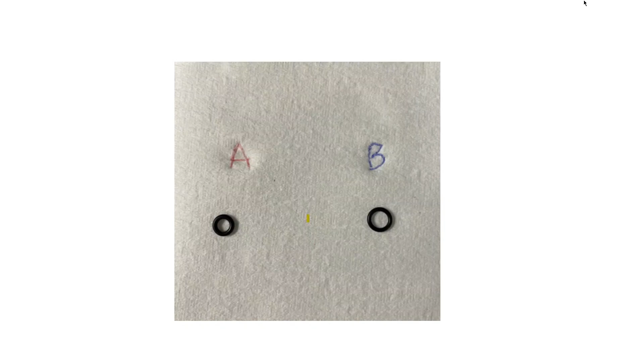So if you're the type of facility that lets caregivers change the O-ring, know that there is a big difference in the O-rings of any manufacturers, because connectors for the manufacturers are scored so that you can't connect bicarb to an acid. All of them, regardless of what company. Okay. So note that these are 2 different sizes. If you put one or the other into that connector, guess what you get? Conductivity issues.